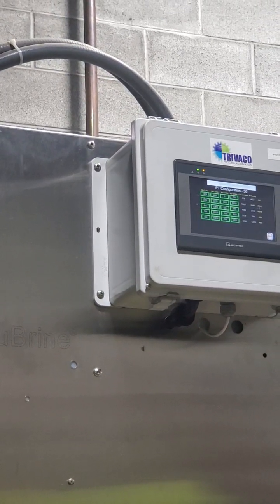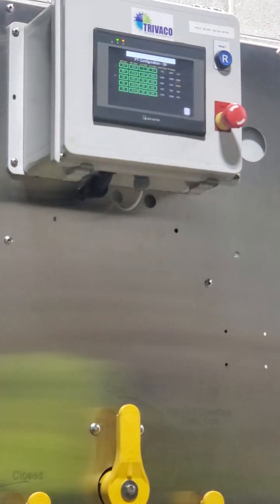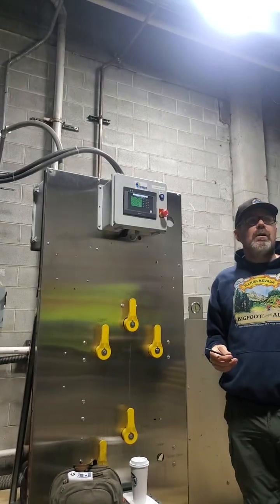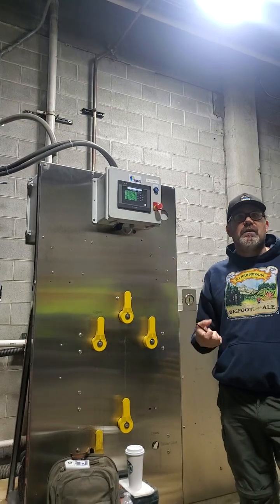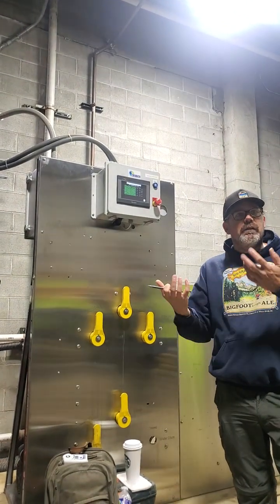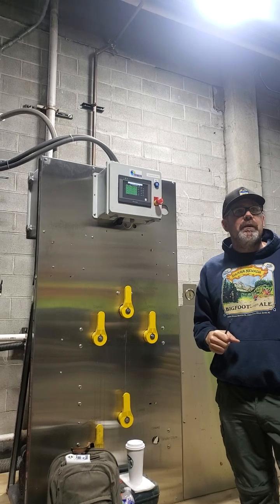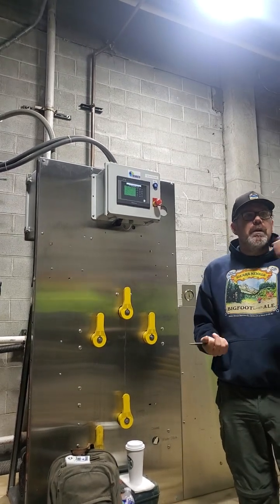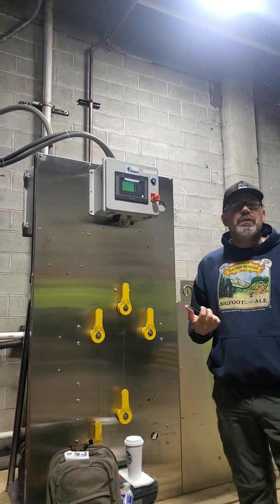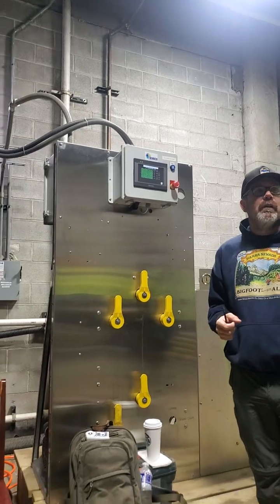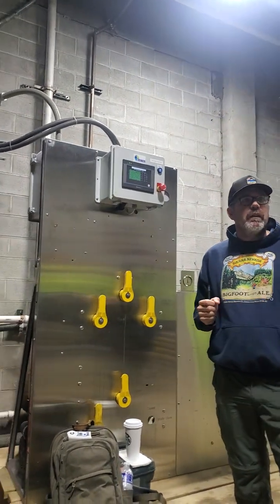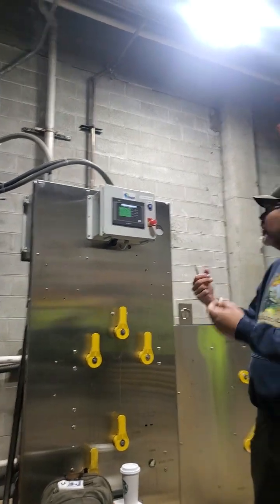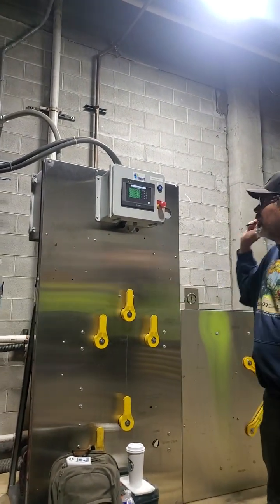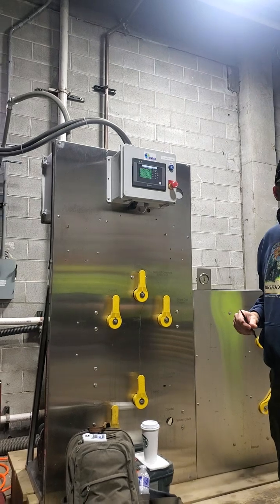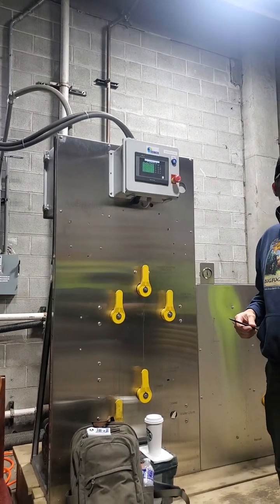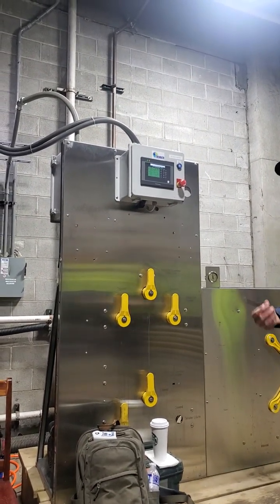Does it happen often, or is it a rare thing? You'll see more failures outside, because those transducers are usually sitting up there uncovered and exposed to the elements. You get sideways rain, and it'll maybe corrode the wire. Mostly, corrosion is what causes it to fail. It's those little connectors inside that fail and the wire breaks out. So in here you'll probably never see it, unless somebody cavemans the thing and breaks it.